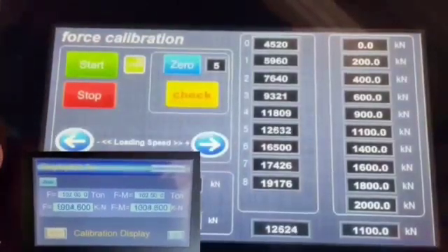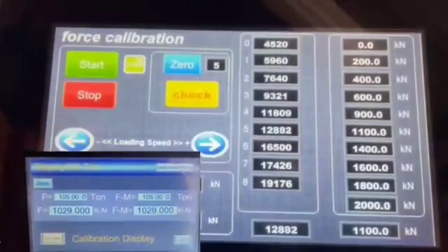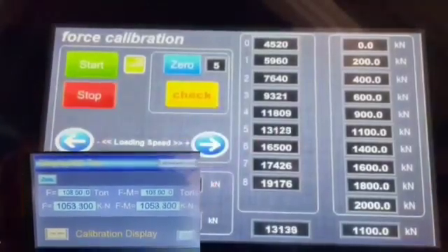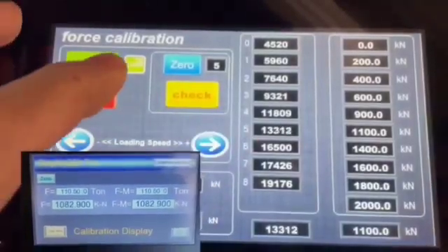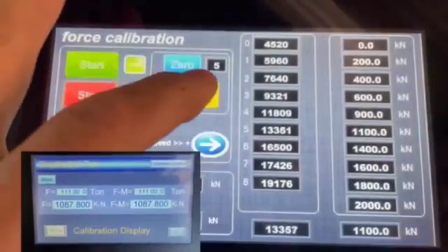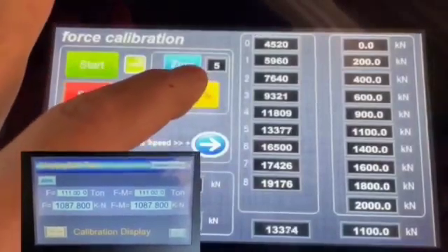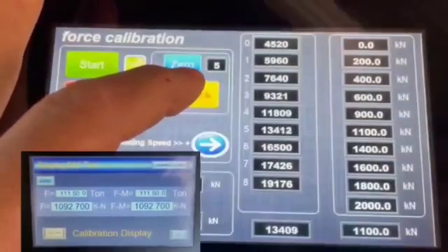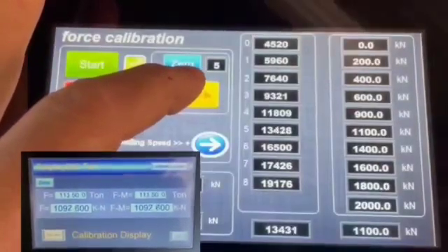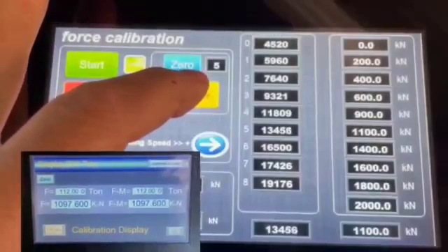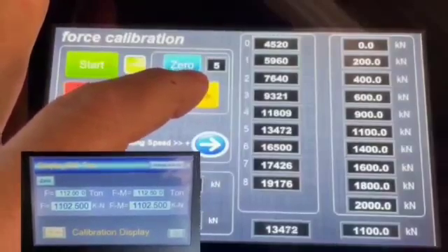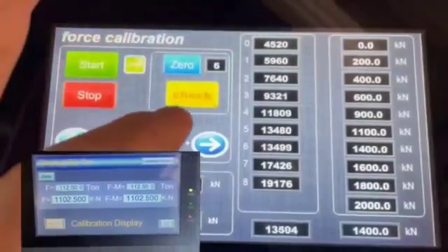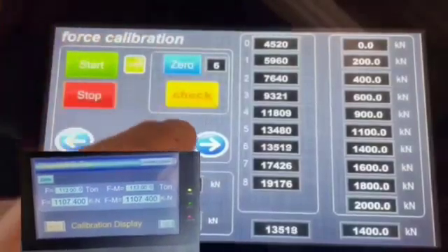Right now it's 900 kilonewtons, and then I go to the next point which is 1100 kilonewtons. I'm waiting for the load cell to show 1100. Again, I sped up this video, and now I'm very close to 1100. Check.